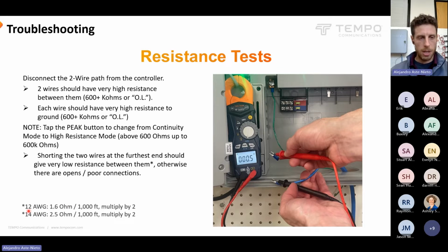So most common is 14 gauge, which is 2.5 ohms for every 1,000 feet. But obviously, there's 2 wires, so we have to multiply that by 2, because there's a certain amount of resistance going out and then a certain amount coming back to our other probe. For 12 gauge, it's less resistance, 1.6 for every 1,000 feet, multiplied by 2. If you have a higher number than that, that indicates there's a bad splice and there's corrosion in that splice, or there's something else adding resistance, but typically it'll be a bad splice.